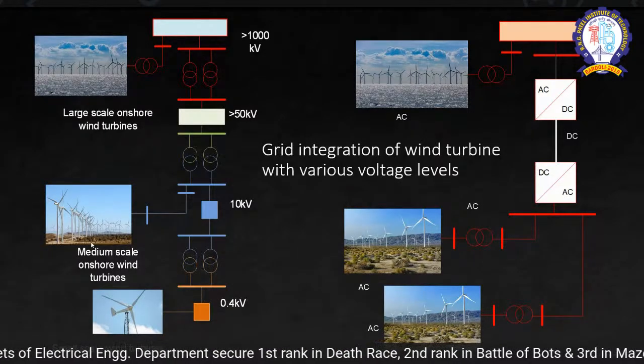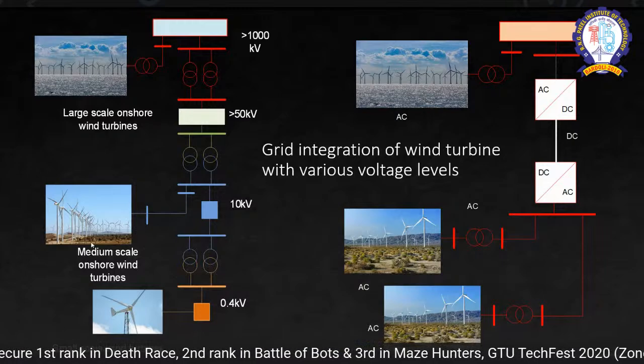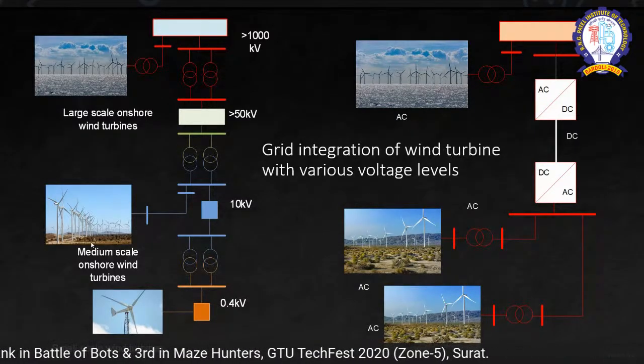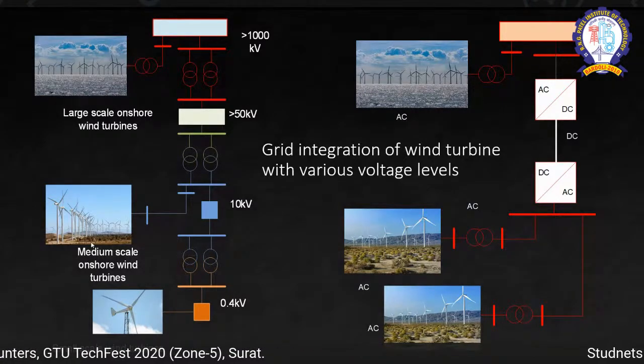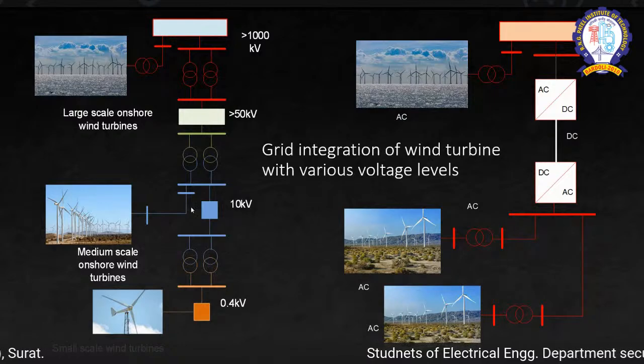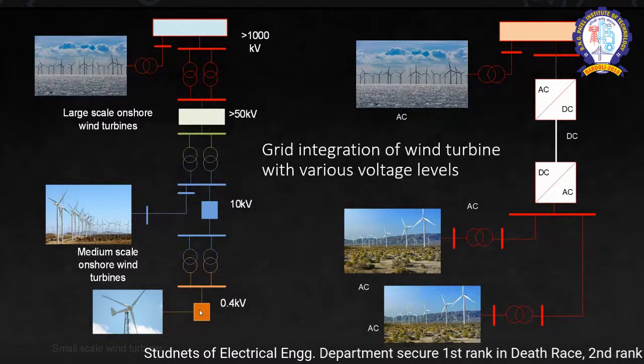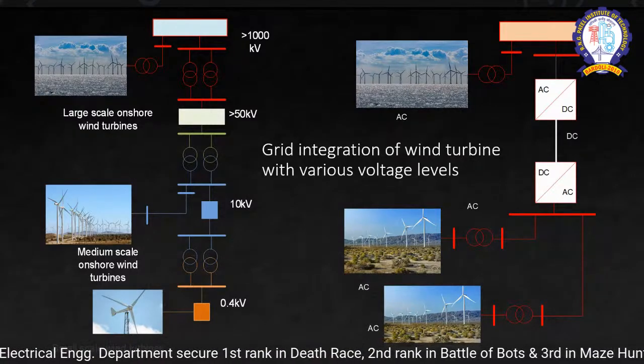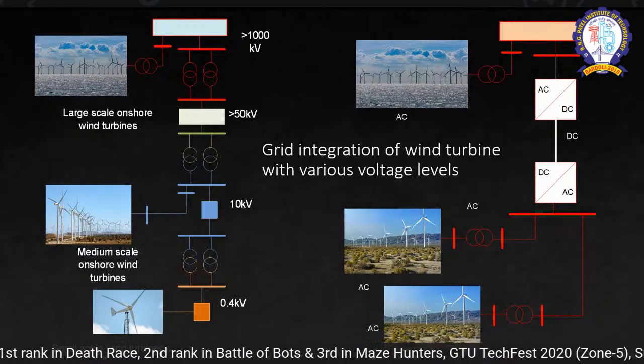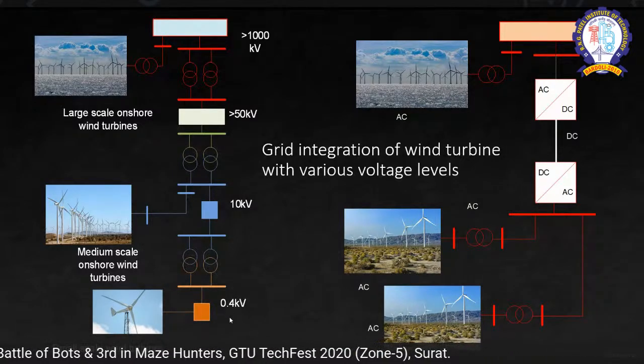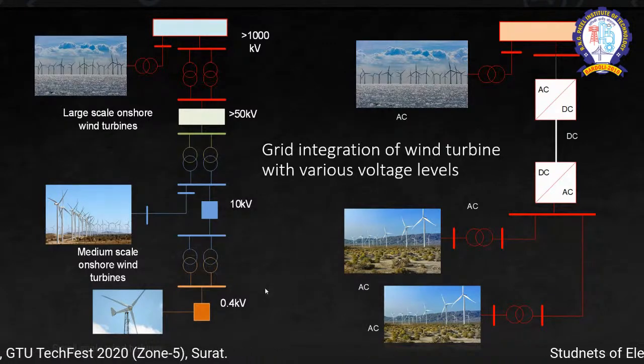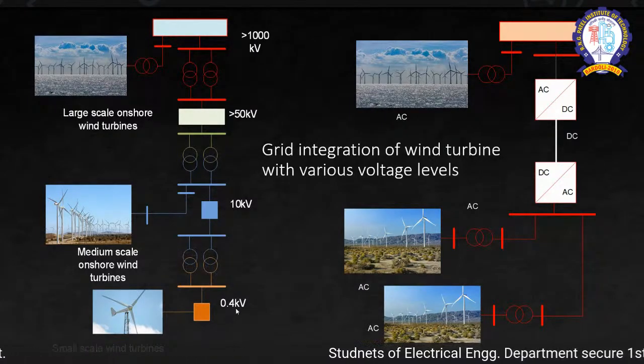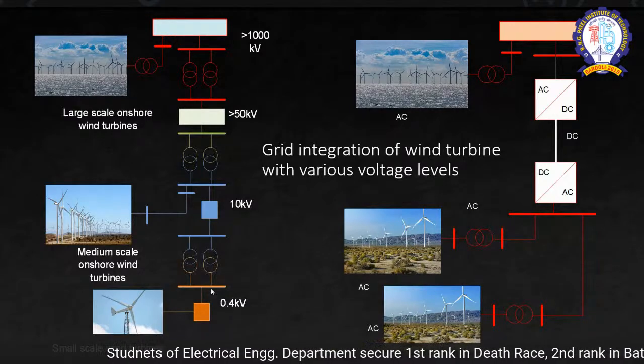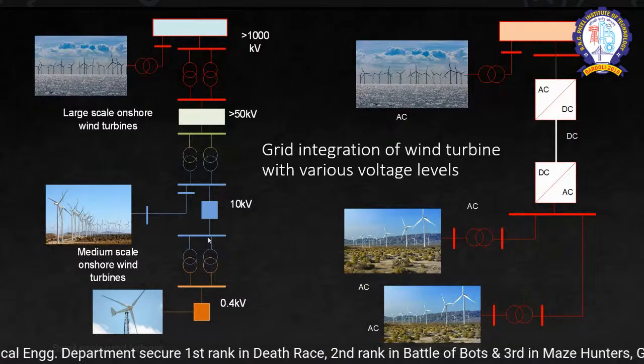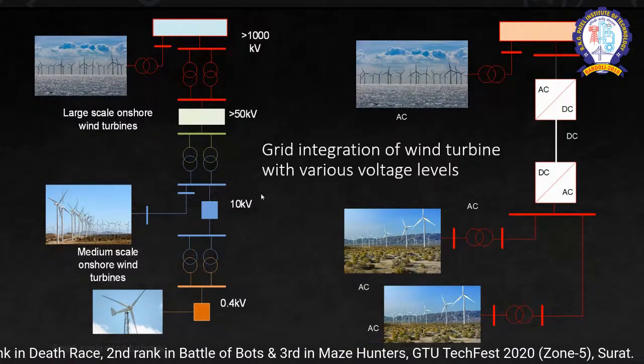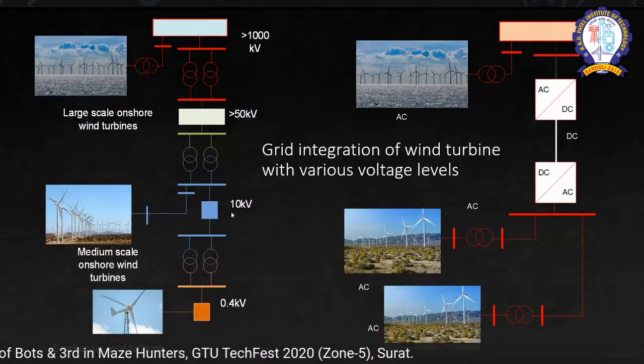Now we have three categories. For the small scale wind turbine, if you need to penetrate the power into the grid, we need to maintain the frequency and the voltage constant. For the frequency regulation, the frequency has to be maintained at 50 or 60 hertz, depending upon the country. For a small scale wind turbine system, we have a range of 0.4 kV, plus or minus 5%. In that case, we have a 0.4 kilovolt voltage rating. Then we have a transformer. In our case, it is 11 kV. In other countries, they use a 10 kV grid.